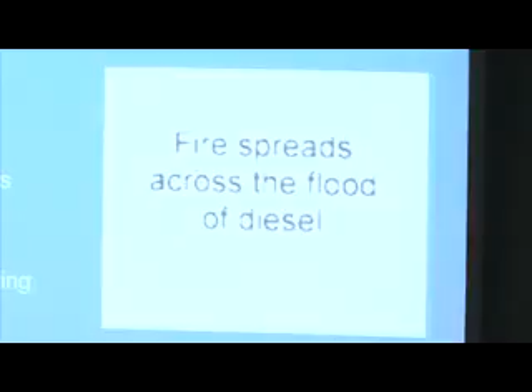So that's after 2 minutes. We have a lot of diesel coming out, and very shortly out of the right side of the container we get a major - there it is. So that bunding tray is pretty much useless now, that's doing nothing for us. And we've got 800 litres of diesel coming out. Yes, it has a high flash point, but as I said before, once you've got a high flash point liquid involved in a fire, you get this.